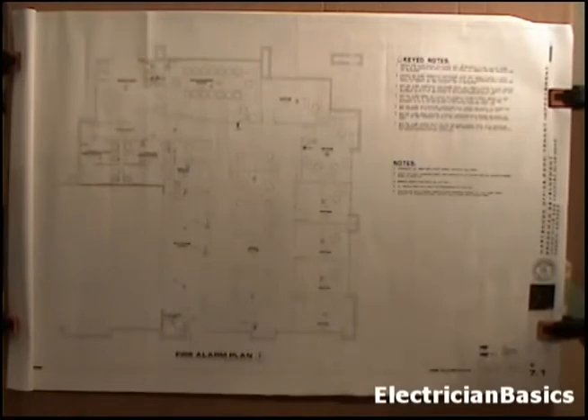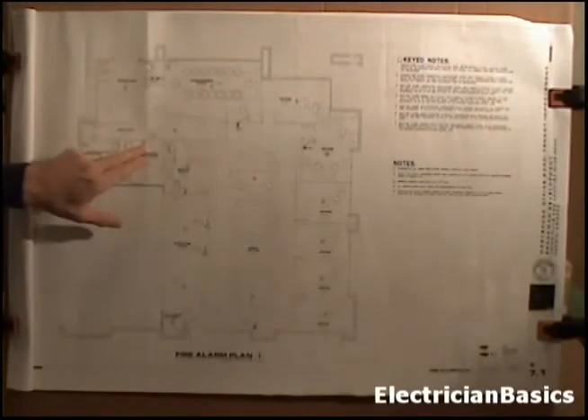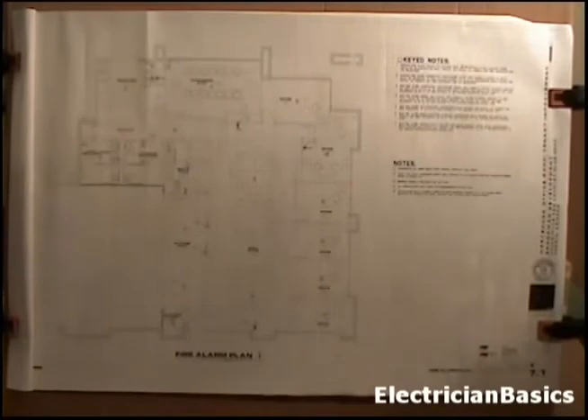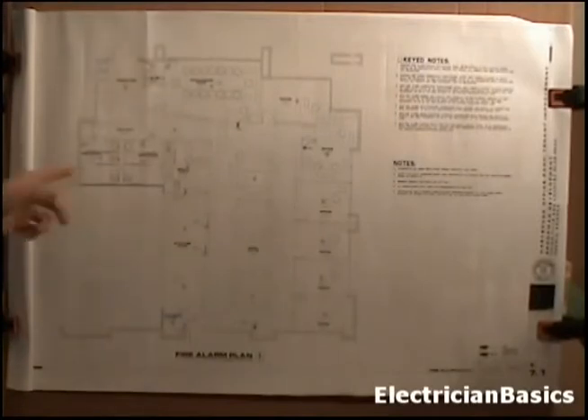Note 4, right here, now this is in the bathroom. It's got a small circle with an X, and it says new fire alarm strobe only device, so there's no horn in there. Now the reason for that, if you're in a very enclosed room like this and that horn goes off, it's going to echo in there, and it's really going to hurt your ears.